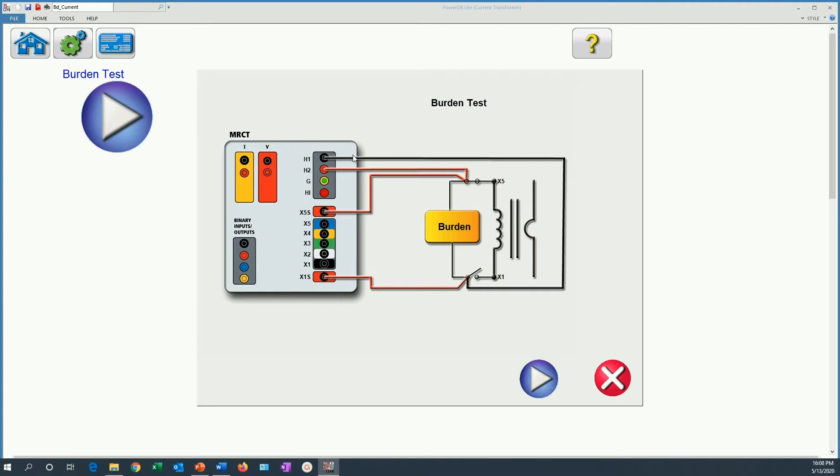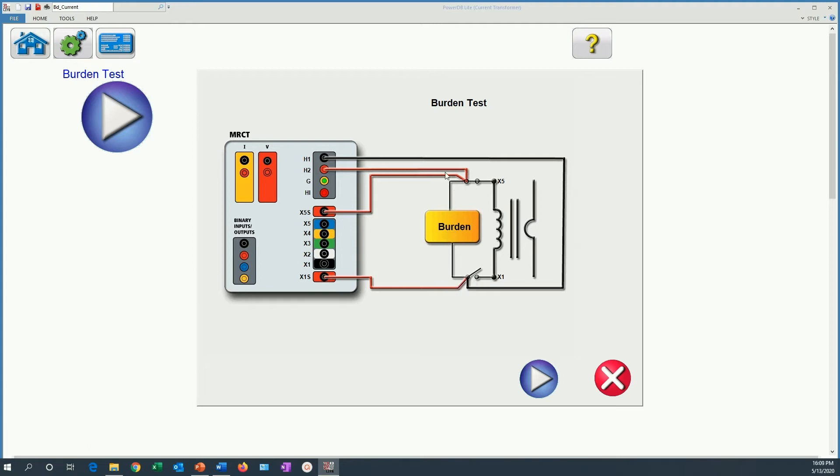Now remember, when we are testing the burden, we are not testing the CT itself. What we are doing is a test to the load connected to the secondary circuit of the CT for which we are going to inject a nominal current to that load. And we are going to measure the voltage drop across that load while we are injecting that current. And the multiplication of both is going to be the secondary burden in VA.